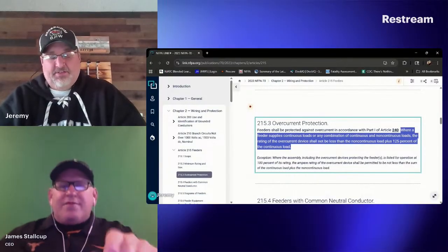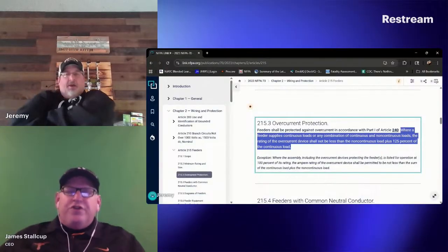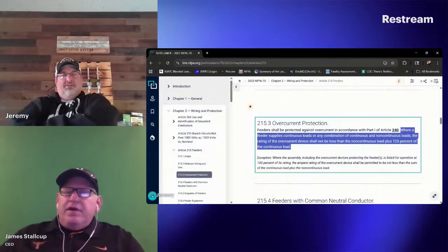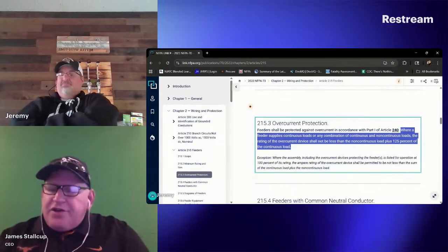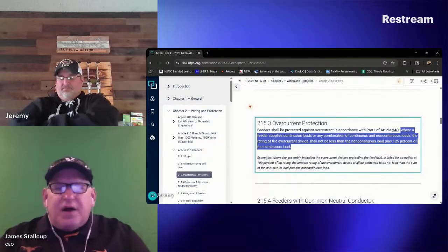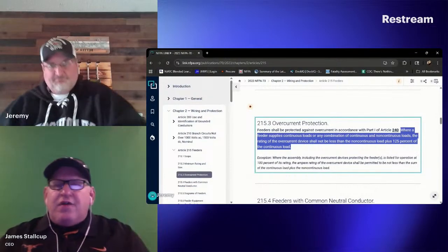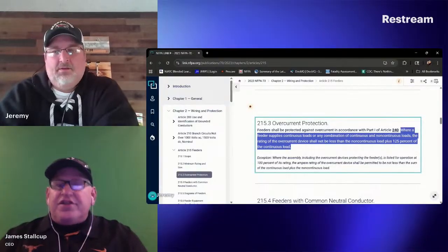See, this is what I'm talking about. You're picking and choosing where you want to apply that. How? I just told you. I do branch circuits, feeders, services all the same way. Once I size those conductors, then that overcurrent device is based on those conductors. I'll prove it.